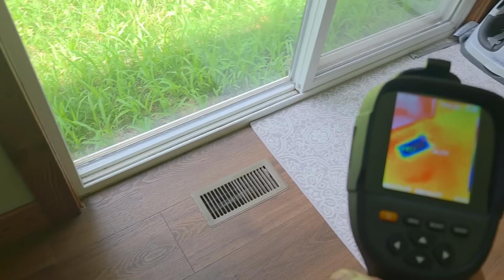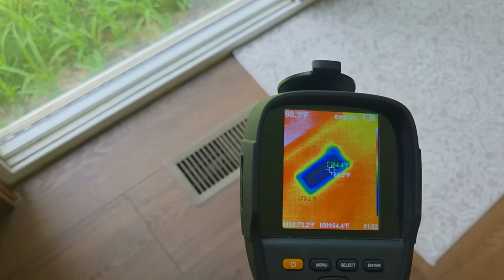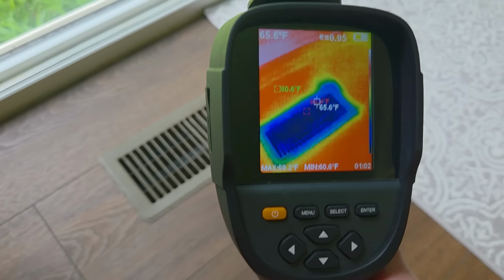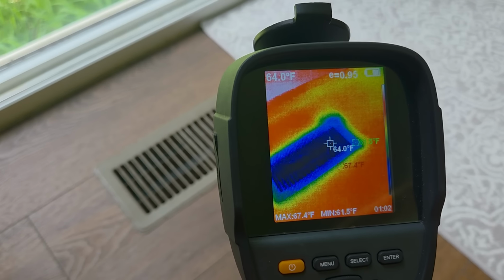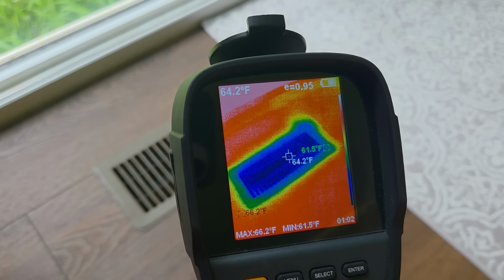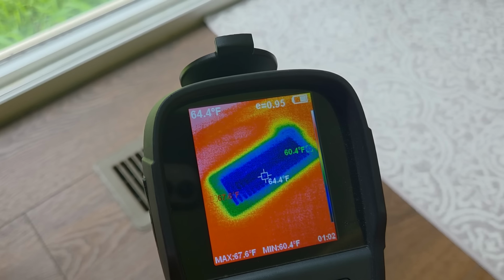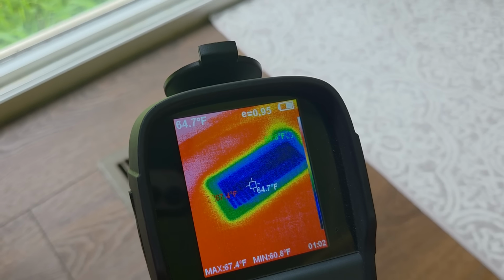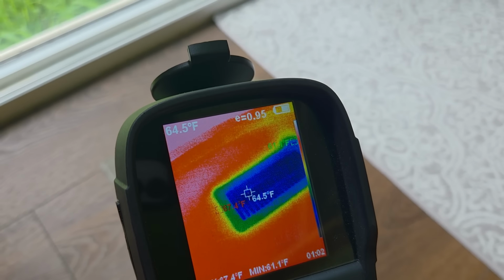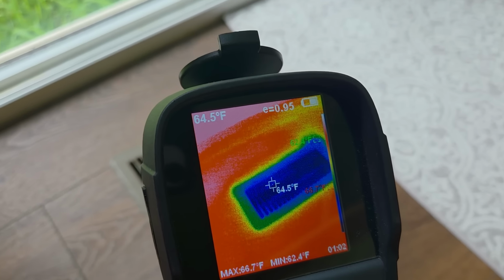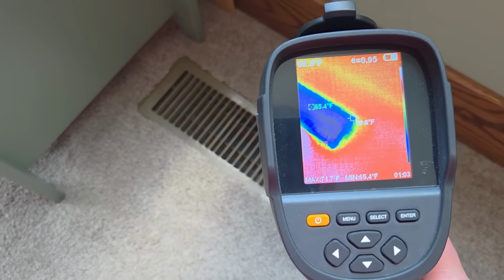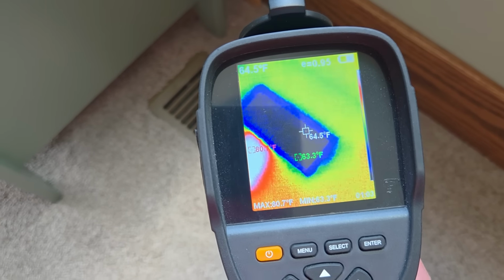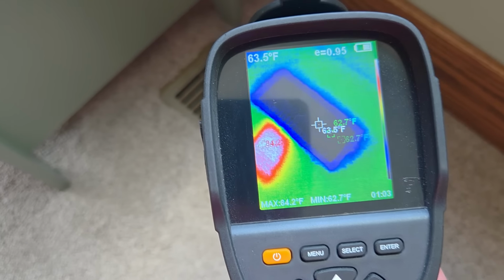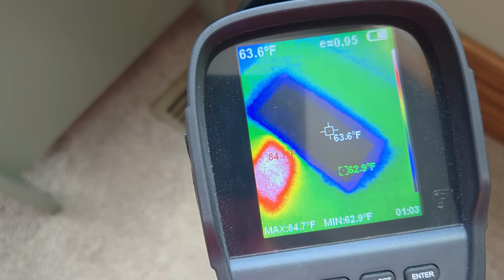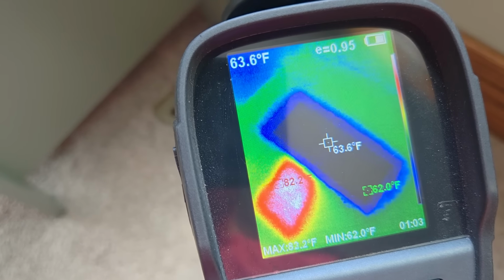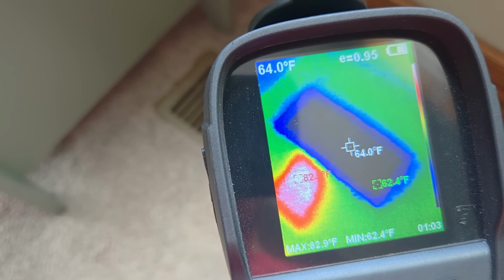So now it's time to check what the temperature split is at the registers upstairs in the house. Now, I forgot to get a video of the return air, but it was reading about 72 to 74 degrees, same as it was downstairs. I'm using this thermal imaging camera, and I know these things have a bunch of different settings in them. I'm not quite sure I'm an expert on it. I believe I had my emissivity set to about 0.95, so take that for what it is if you actually know anything about these. And then over at the supply air, I'm reading down in that low 60s, maybe 61, 62, sometimes closer to 60.